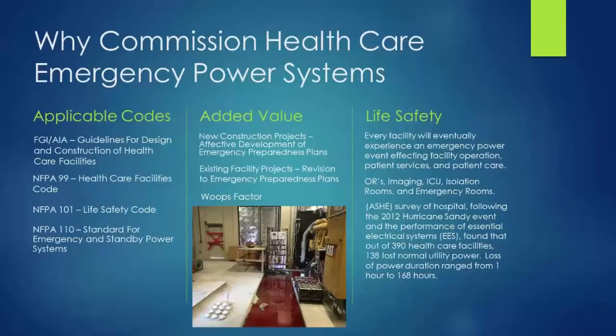The second one follows from the existing facility, and jokingly I call it the whoops factor. In that picture that you see there, I was testing the emergency power system at a facility. I was in the paralleling gear room and needed to check something on the generator. So I walked out of the paralleling gear, into the generator plant, and when I turned the corner to go to the generator control panel, there was a geyser of fuel oil shooting out the top of the fuel oil day tank, which is that white box there in the center of the screen. I wish I could have gotten a picture of it actually shooting out, but this was after we hit the emergency stop button and shut the whole test down.